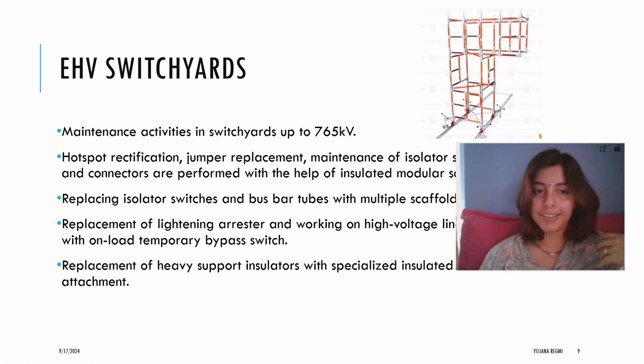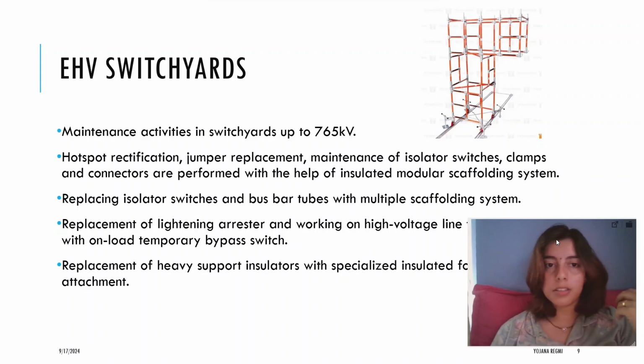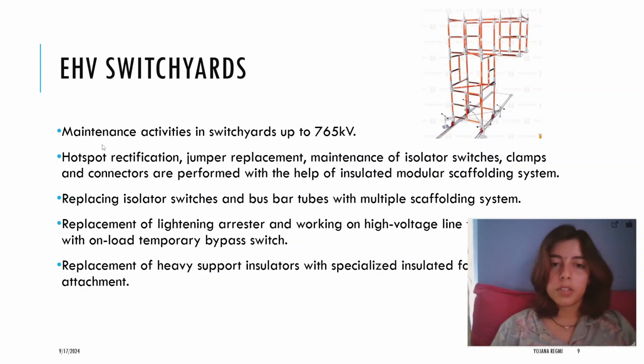The third thing is the EHV switchyard, which is the extra high voltage switchyard, where we can do maintenance activities up to 765 kilovolts. As you see in this picture, this is special equipment called a modular scaffolding system, which field workers can use to do various maintenance activities, such as replacing jumpers or rectifying hotspots on isolator switches. In a switchyard we obviously have isolators, and there are many types, such as center break and center rotating. So we can maintain them.